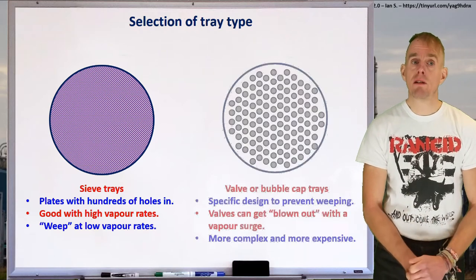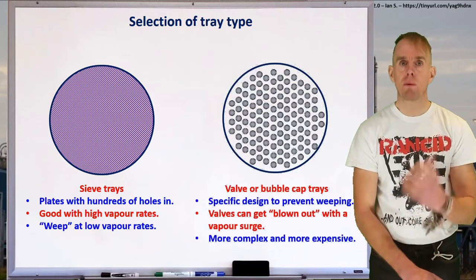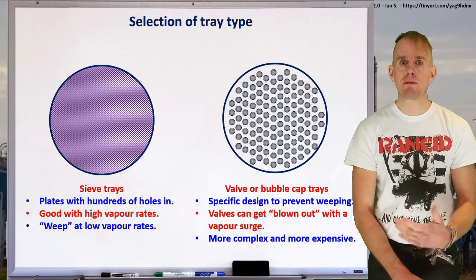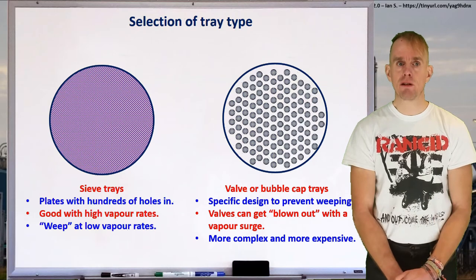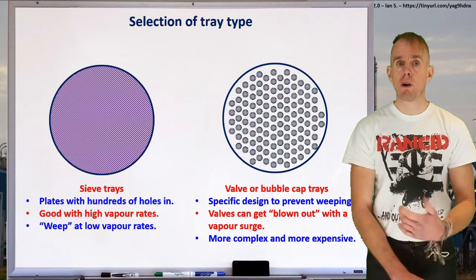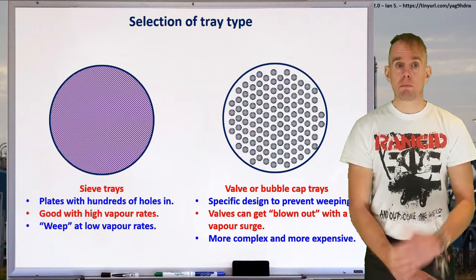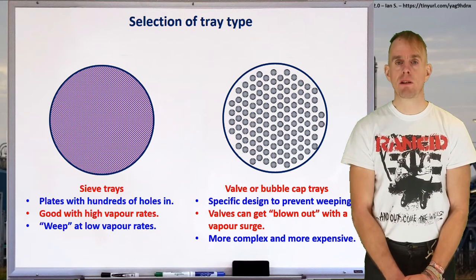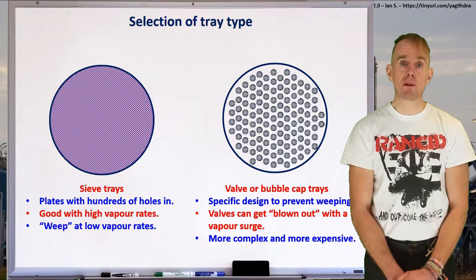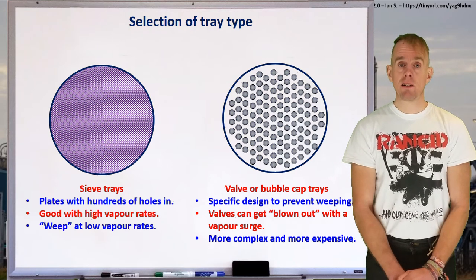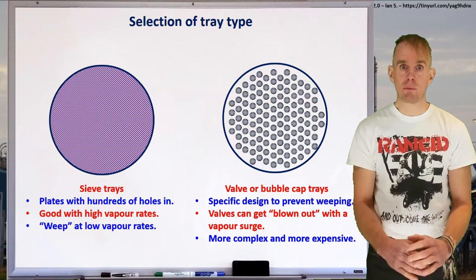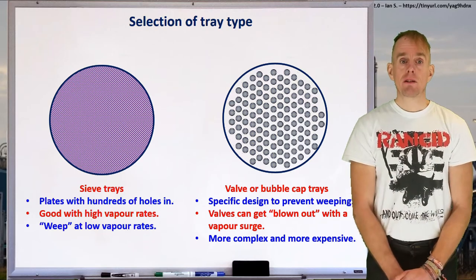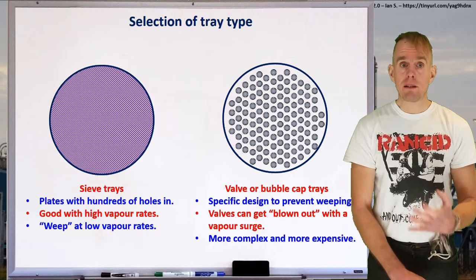Sieve trays are good, cheap, and robust, but they do weep at low vapor flow rates. If you're dealing with low vapor flow rates, you need to prevent liquid from draining through those holes. There are many different designs of tray that allow you to do that, including valve trays or bubble cap trays. These are more expensive, slightly more complex, and can go wrong — if you have a vapor surge through a distillation column, you can quite easily blow the valves out of a valve tray.